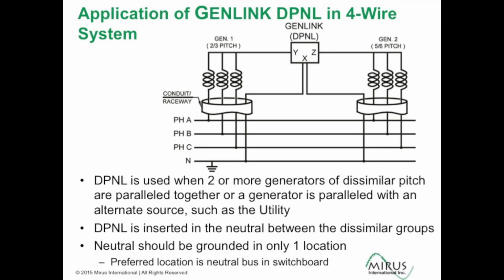Now, when we have four-wire applications, if we have to bring the neutral back, so if we have phase to neutral loads downstream of the generators, then we recommend that the neutral conductors be supplied through the same conduit as the phase conductors for each generator. And that is so that the fluxes that are generated in the phase conductors will cancel with the return flux going through the neutral when we have single phase loads. And this is good common practice in any four-wire application.